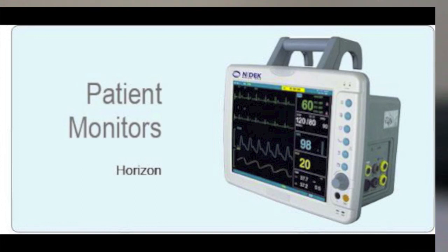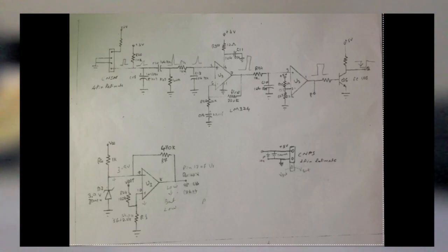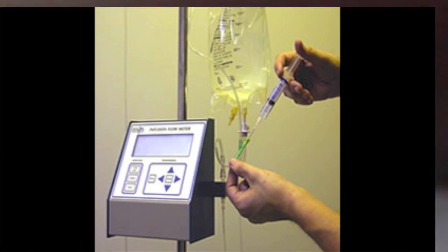There are also added features of a real-time clock and alarm settings by which the patients can be monitored, and hence any emergency like a drug overdose or underdose can be avoided. The rate of medicine infusion can be controlled by a roller available on the IV tube. The sensor is compatible with any kind of IV tube set used. Hence, the infusion monitor provides flexibility to doctors and nurses with a large number of patients.